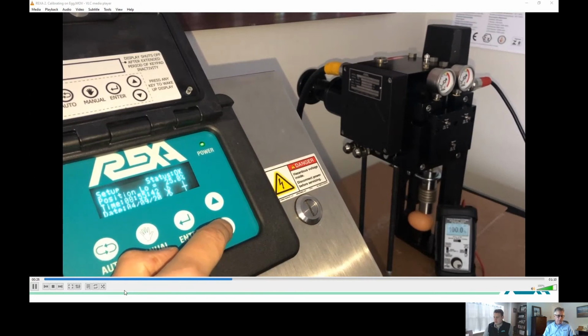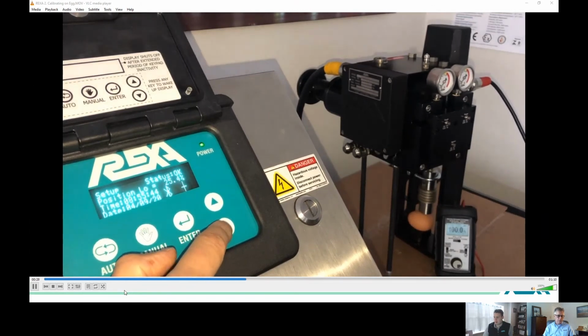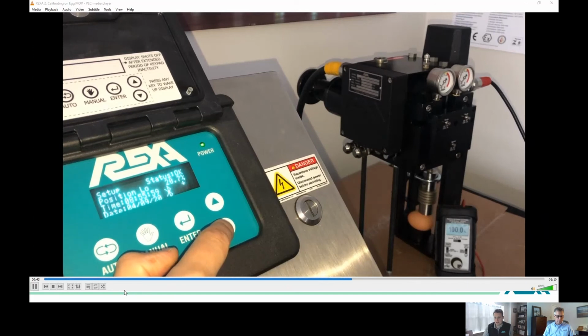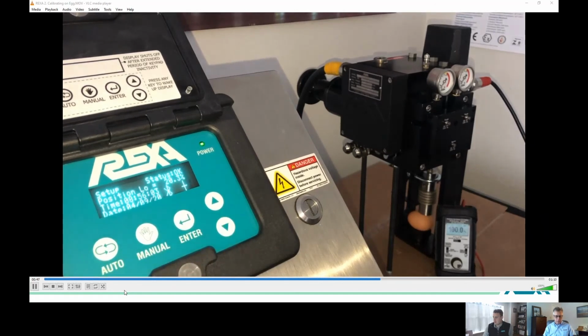When you get close to the position, you can see we're making very small position changes in the calibration. Notice the pressure isn't changing because there's no load against the actuator. In a position-based system, it's going to go to position, and the pressure is only built as needed. So here, 20%, and we just heard the egg crack.